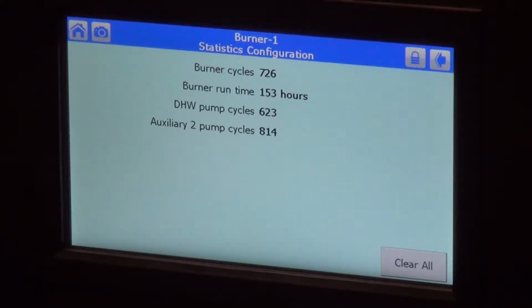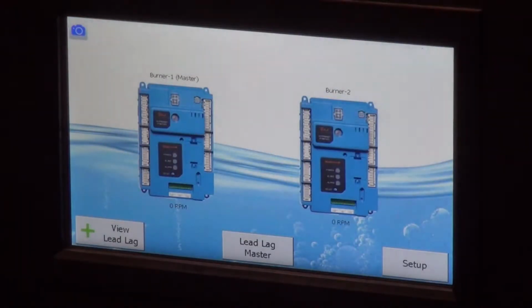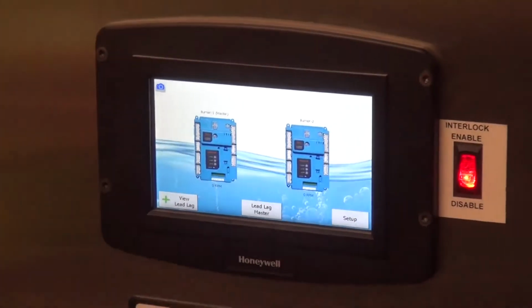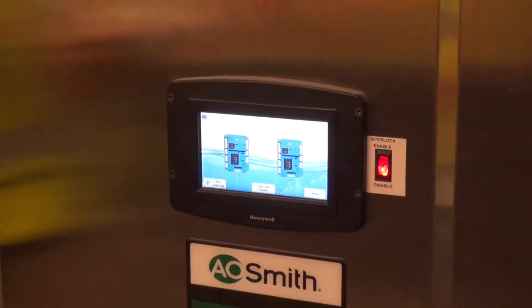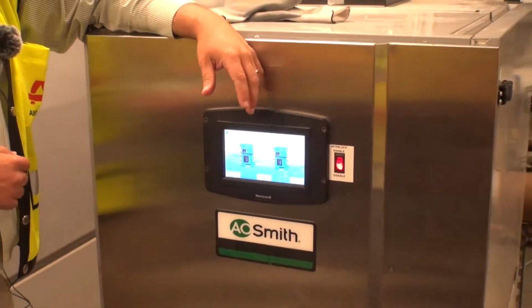We've got a 1-year part, 1-year labor associated to each one of these, and that's based on when these actually go into full operation. These have received a factory startup already, so they are approved by the manufacturer. That came when you purchased these boilers. That came with an authorized factory startup. We have all of those documentations registered, by the way, back at A.O. Smith. So if anybody needs to see the run history of when they did the startup, that is all logged back there. And what they'll end up doing is they come in, they check flue temperatures, they check gas pressures, they check boiler configurations, write it up, get it all approved, and we're basically up and operational.